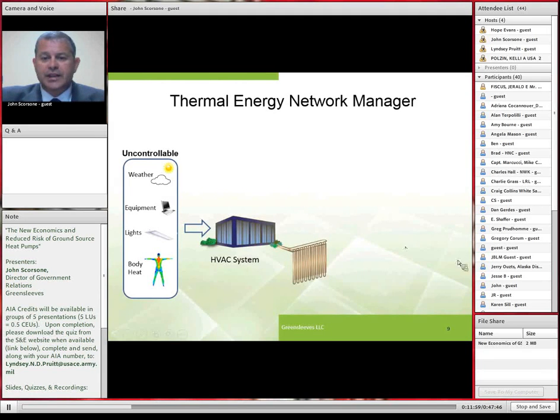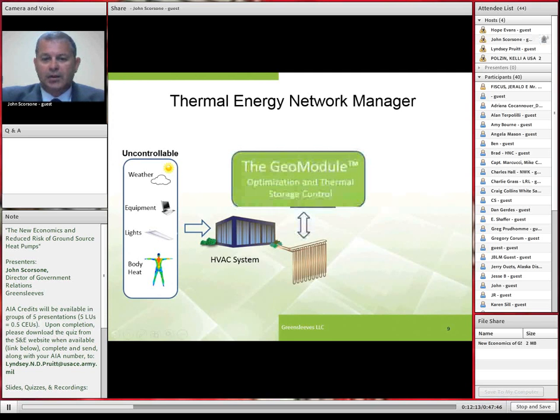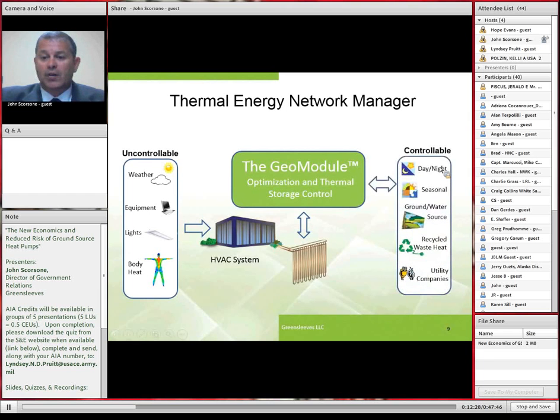With the Greensleeves GeoModule, we add a brain to the system that makes decisions using intelligent algorithms to decide when and how to reject the excess heat with the use of a fluid cooler or a cooling tower. By changing the time of day or the time of year we get rid of this excess heat, we can now make predictive, optimized decisions for a thermal network. This process allows us to store the excess heat for summer and use it to make hot water or get rid of it at an optimal time in the winter.